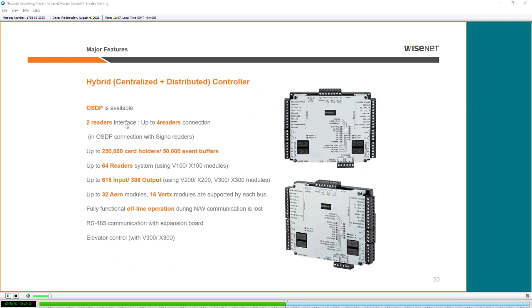All right. Now let's look closer at the hybrid controller. If you are going to use it as a centralized method, that means the central controller will have TCP/IP, right? This will go to the software. Then the subcontrollers are connected via RS485. Where is RS485? It's here, port number 1, port number 2. So there are two RS485 connections.